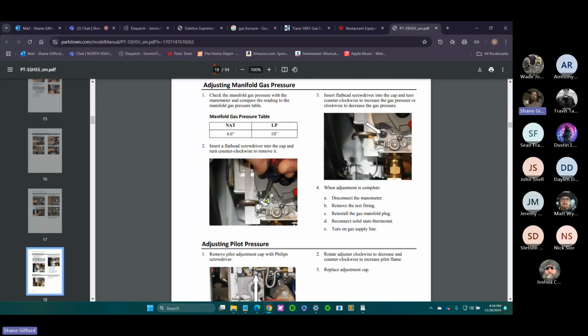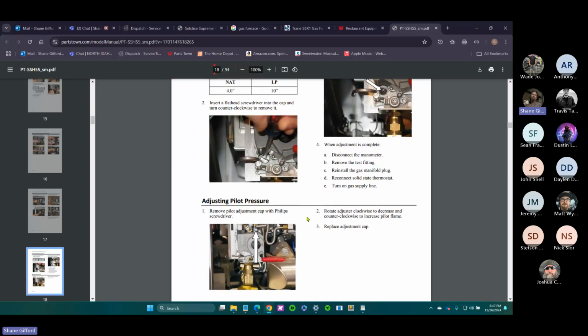But here's a close up of how to adjust your manifold pressure. You'll see a screw. Take that off with a little flathead, and it'll expose a little plug. Beneath this plug is a spring, and beneath that is the top of the valve. When you screw this down, it pushes force on the spring, which pushes force on the diaphragm to open that valve. You're also going to want to hook up a manometer before you touch this screw, because you've got to record your data before you make a change, then make your change, then record your data, so you can show the before and after.